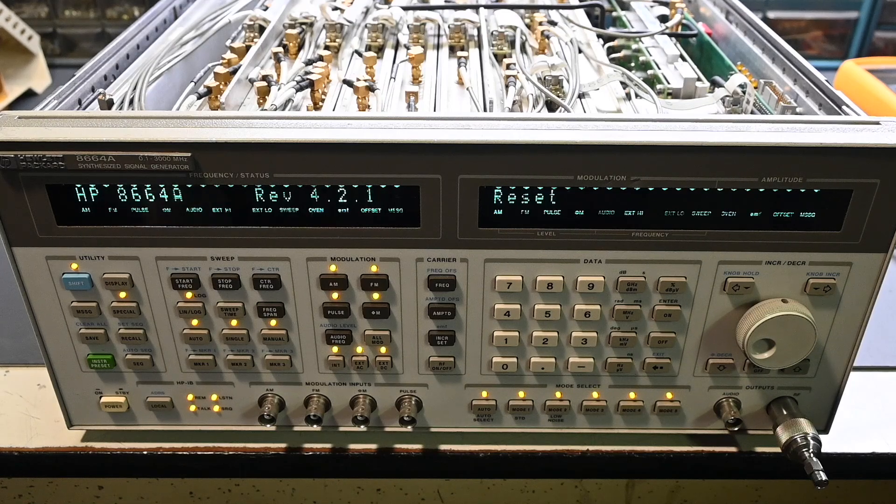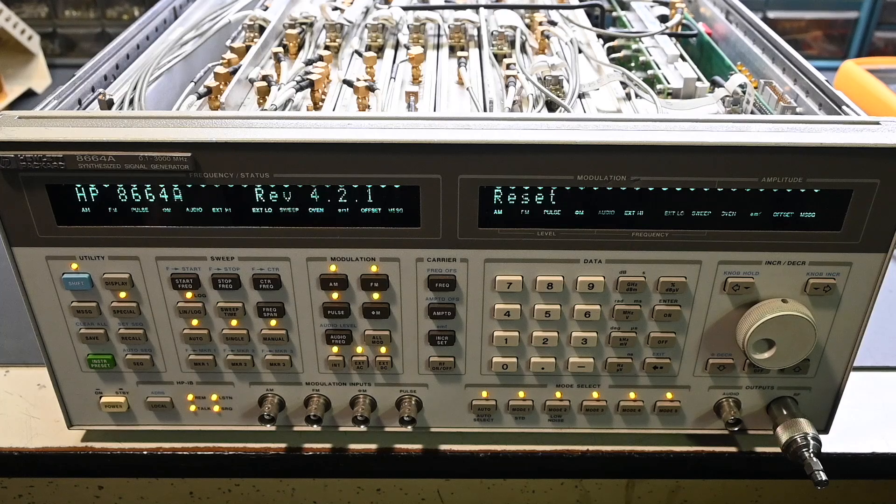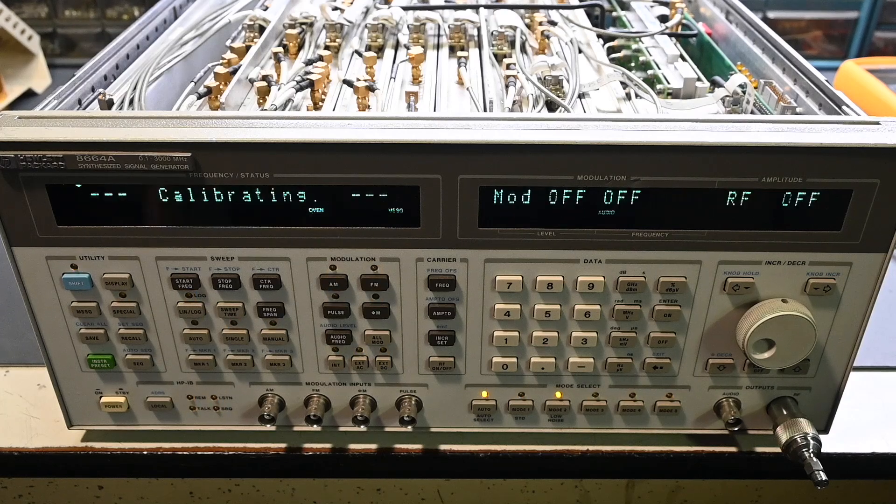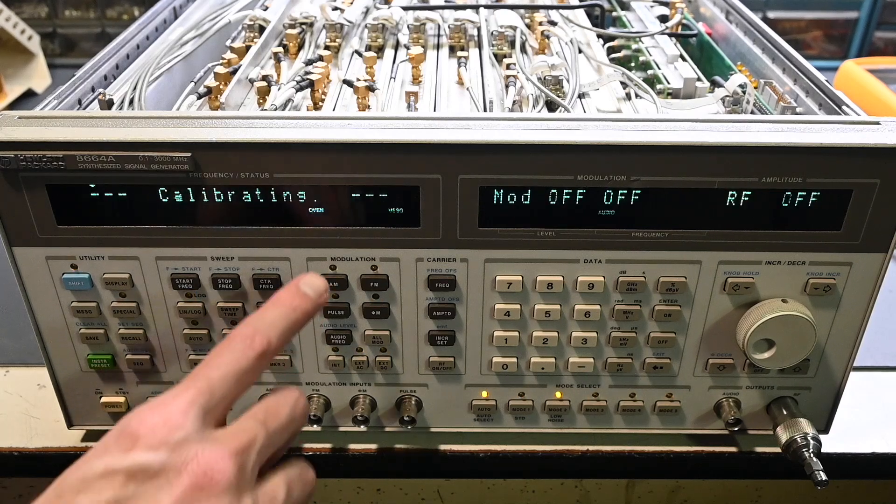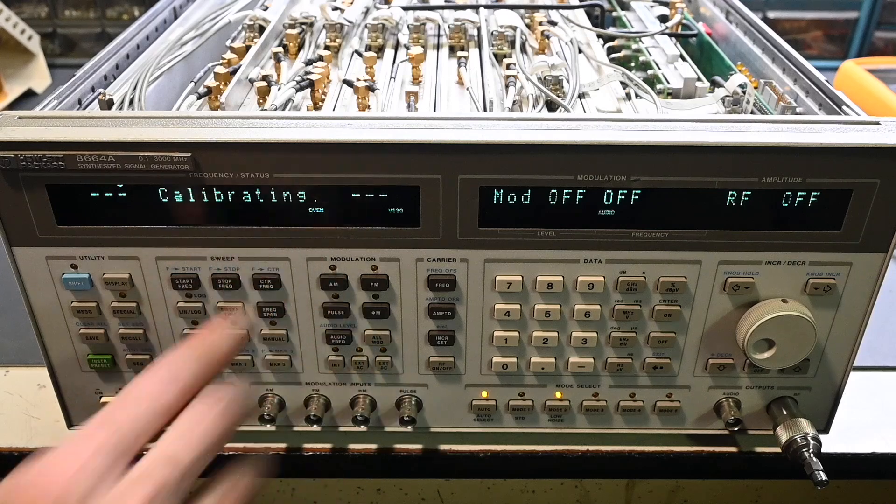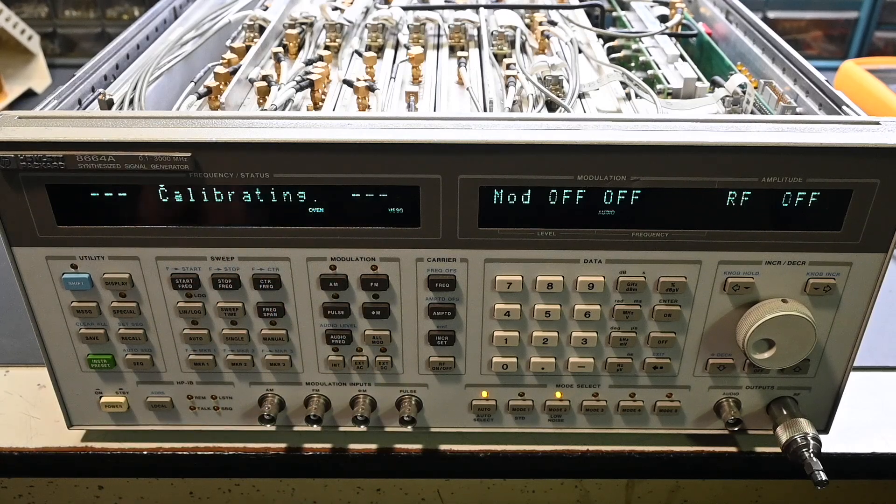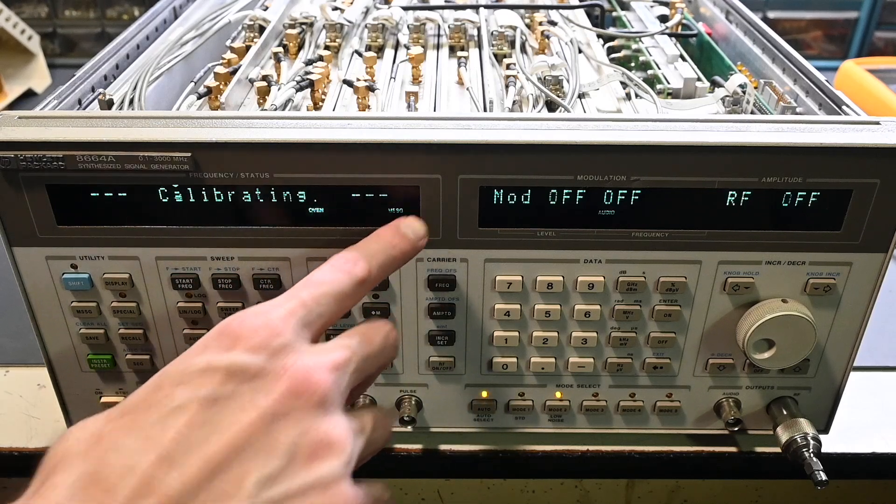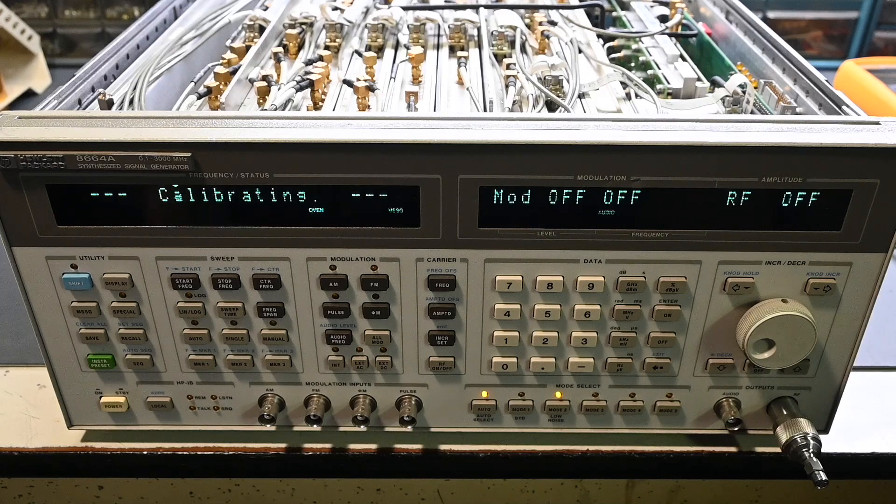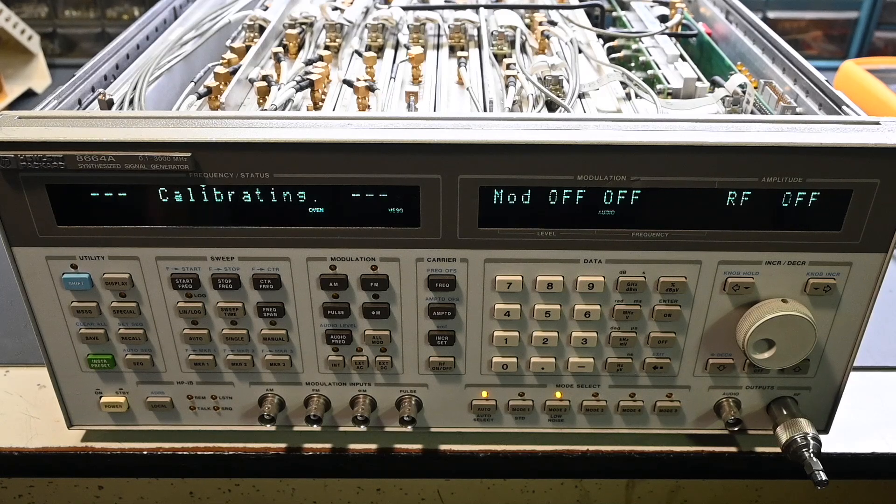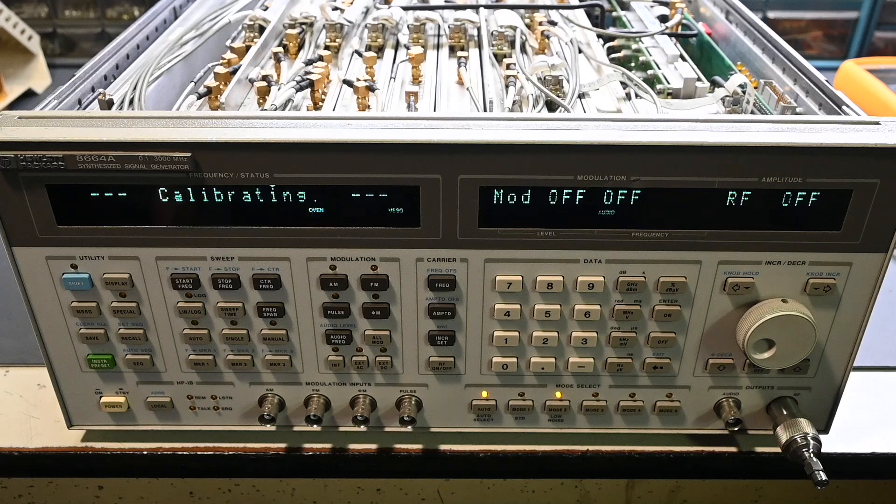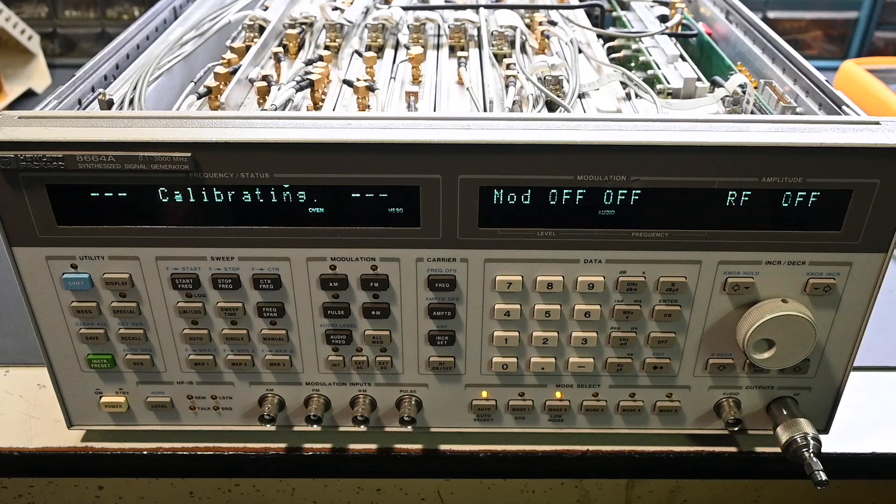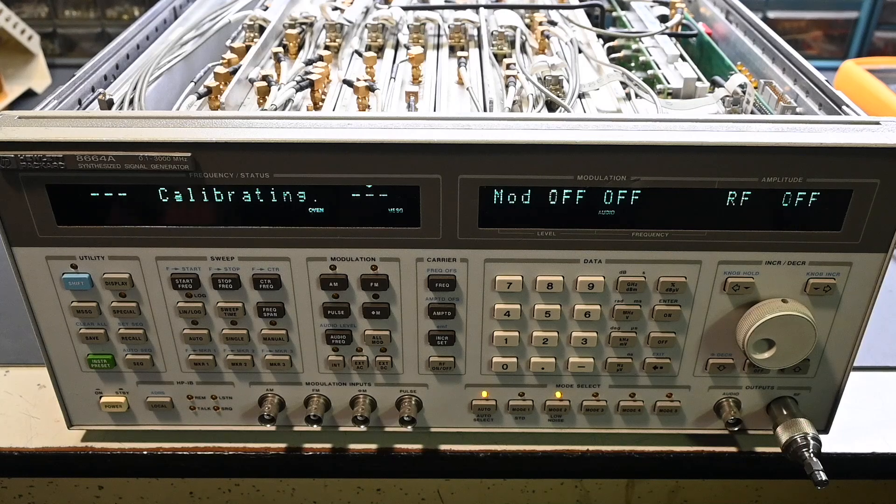So it should go into the self-calibration routine, give it a moment here to start up. Yes, there it goes, so calibrating, and it says oven because the oven has cooled a little bit, and that indicator will go off. And we'll take a look at the messages, and it should just basically say that the user memory was cleared, there shouldn't be any other error messages if everything's working correctly. So the calibration routine takes a little bit of time, so we'll continue on once that's complete.